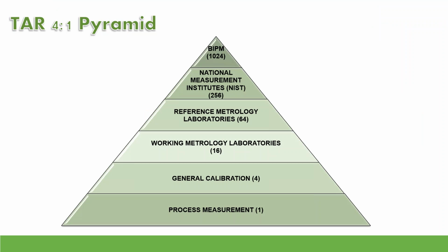TUR, we've talked a little bit about TUR, test uncertainty ratio. That is very maintainable. However, TUR or TAR, test accuracy ratio, developed by Jerry Hayes in about the 50s and 60s with the Navy. TAR, not so much. Because what we said was, hey, I want a lab that's 4 times better. And that works short term, all right? I have a process measurement that's 1%. If we do this down here, then I need something to be 0.25% right here, right? 4 to 1. Then I need something to be 0.0625. And it just keeps going and going, getting lower and lower.